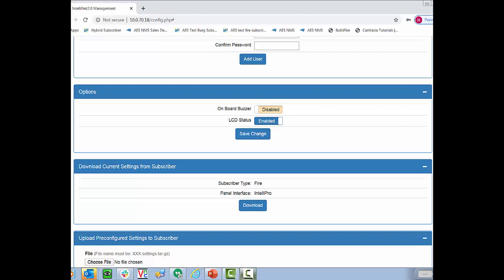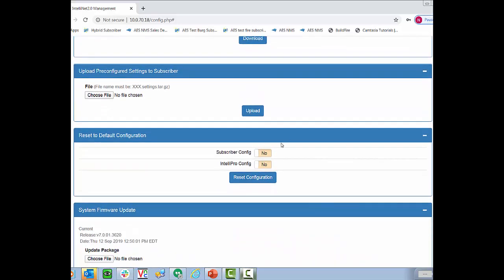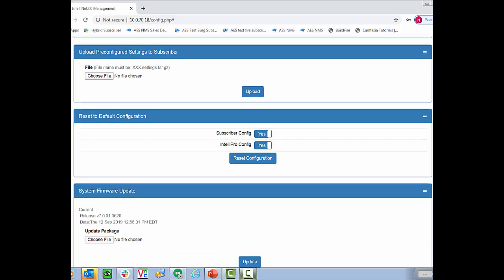One of the other more handy features of our 2.0 subscribers is you can download the current settings from this subscriber and then put it onto all the other subscribers. So if you have a set way you configure all of your subscribers you can get one subscriber with all your users names password zone settings everything set exactly how you want it and then download it from that subscriber and use a USB thumb drive to upload it to all the rest of the subscribers. If you ever want to default a subscriber you'd select these two flags and then hit reset configuration and this will default the subscriber. Note that it will not remove the cipher code or the sub ID. Everything else will be returned to default.